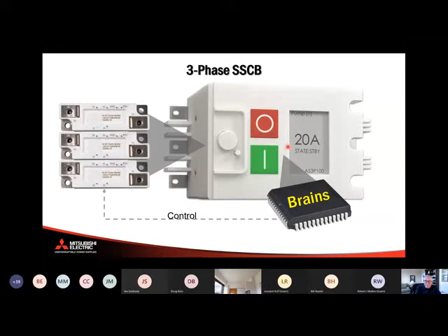So you're looking at a panel board here with 15 amp, 40 amp, 100 amp circuit switches in here. You can actually digitally remote control these switches, these breakers, with an unlimited amount of operations, because we're not putting any stress and strain on the components proper to a circuit breaker. And you have a dynamic time current curve.